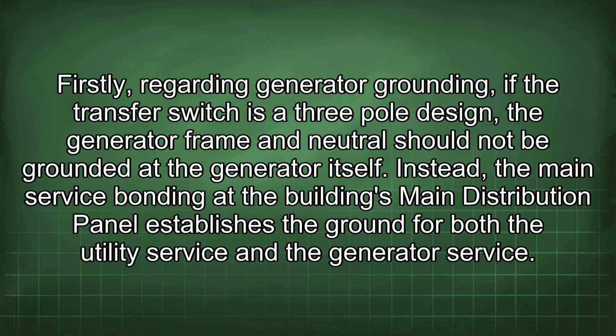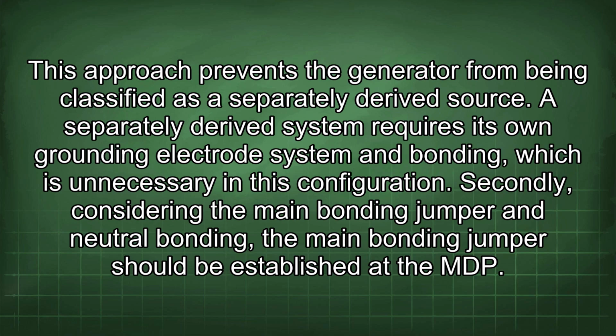Firstly, regarding generator grounding, if the transfer switch is a 3-pole design, the generator frame and neutral should not be grounded at the generator itself. Instead, the main service bonding at the building's main distribution panel establishes the ground for both the utility service and the generator service. This approach prevents the generator from being classified as a separately derived source. A separately derived system requires its own grounding electrode system and bonding, which is unnecessary in this configuration.